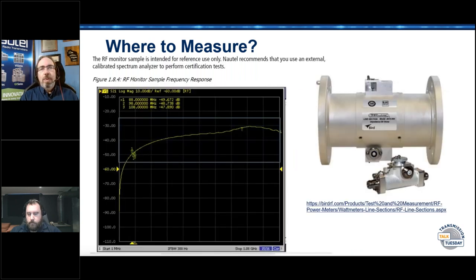Now this is where I quantify and backtrack on what we just said. We do have a typical correction curve shown in the manual. This is out of the install manual, might be pre-install—Adam, do you remember? I opened all four manuals. I opened all the manuals this morning and searched 'monitor' until I found it, because I knew I'd seen it. But it's either pre-install or install. So we do have a little bit of a correction curve in there, and that will give you at least a general idea, but it's not going to get you down to the 1 or 2 dB level by any stretch.